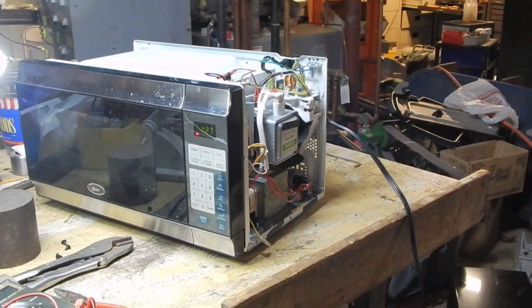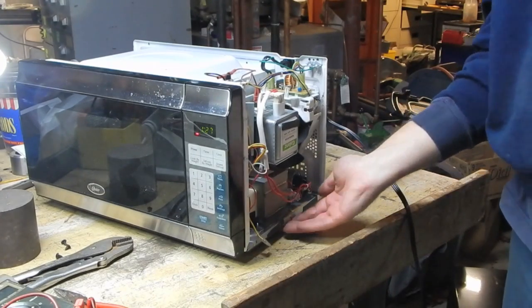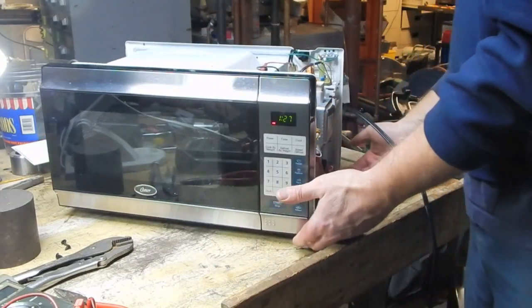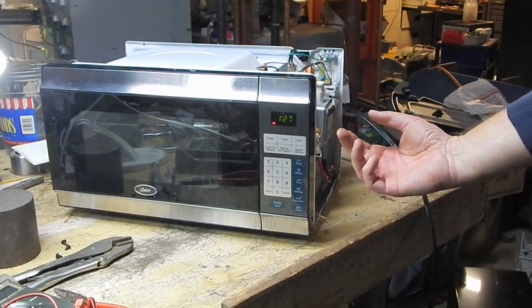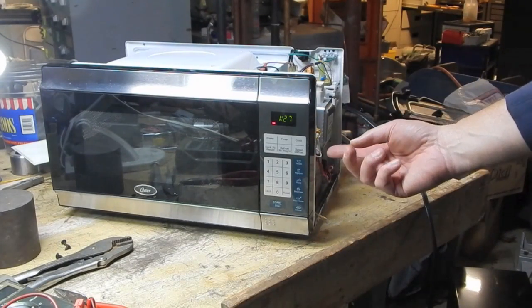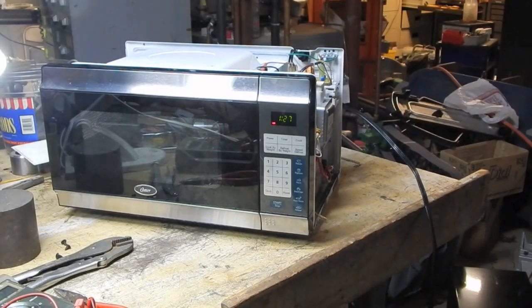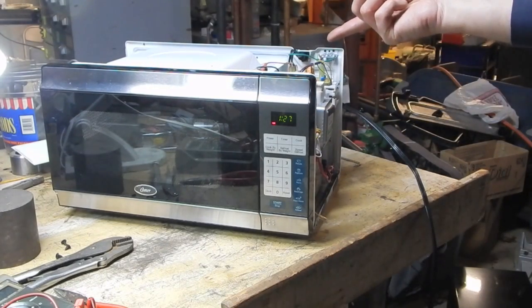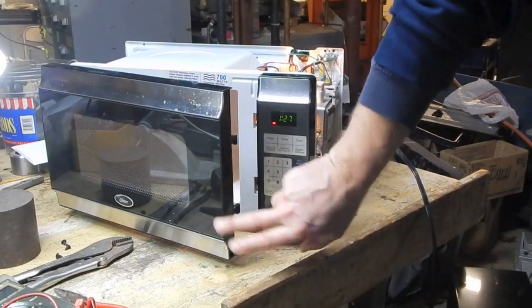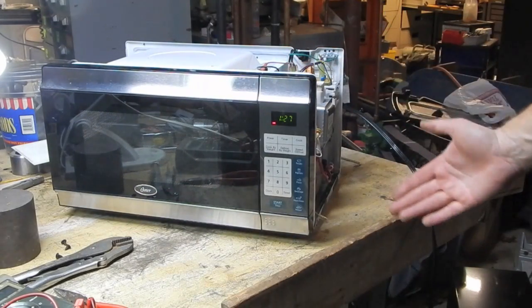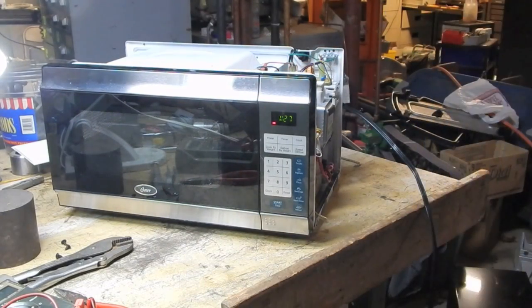All right, so now let's see if my little 3 or 4 amp fuse has got enough amperage to run that fan and the light. Because basically the only additional amperage draw we're going to see when I energize this is, to get extra technical, the voltage involved in closing the coils on the relays mounted on the PC board, the fan, and the light. We already know it can handle the light, so we're just adding that little bit of extra current, and the 4 amps should be able to take it.